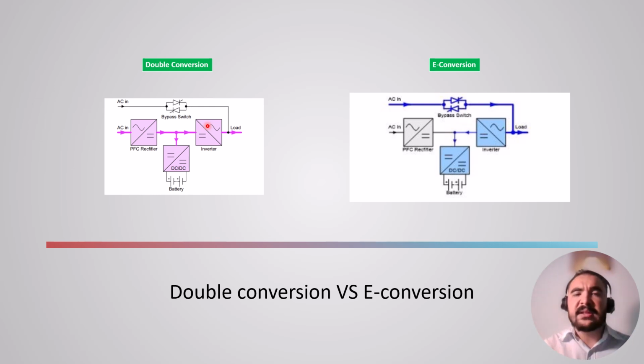I know that this traditional setup ensures the highest level of protection, but it also leads to a slight increase in energy consumption and heat generation. Why is that? Too much electricity is being used, as power is converted twice before it reaches the load. On the other hand, with the e-conversion mode, the first difference is that the rectifier will be off, it's not going to work. The second difference is that the alternate current this time will come from the bypass.